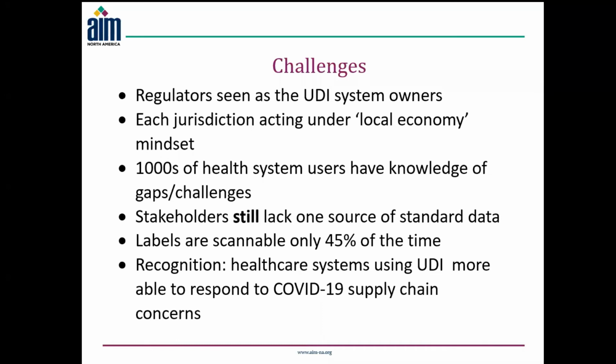A related concern is that even though we live in a global economy, jurisdictions are still embracing a local economy mindset when it comes to UDI. This doesn't recognize the fact that every variation from the original IMDRF principles or data has a significant impact on the end user, and that the end user may not even be located in their jurisdiction. FDA's GUDID is being used around the world today.